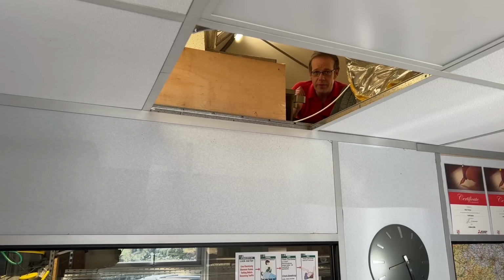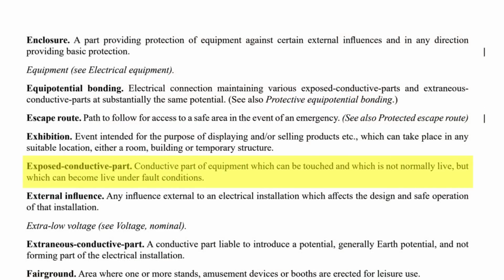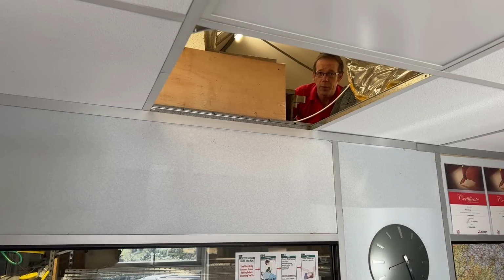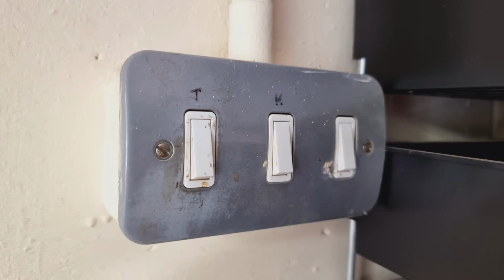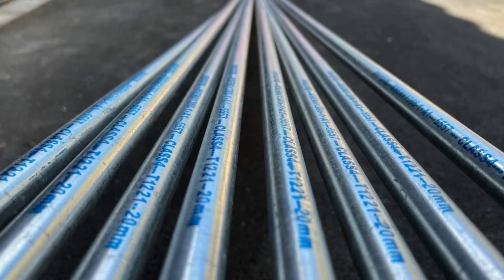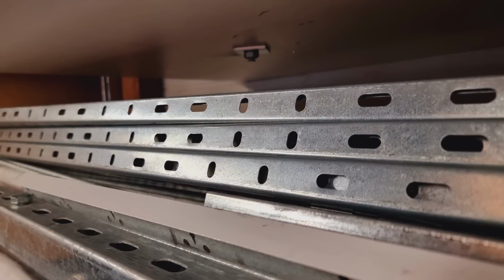Well, there's two types of conductive material in a building that may need connecting to the main earthing terminal of an installation, these being exposed and extraneous conductive parts, and BS 7671 defines them as follows. An exposed conductive part is a conductive part of equipment which can be touched and which is not normally live, but which can become live under fault conditions. The simple way to remember it is that this is a metal component which is actually part of the electrical installation and which can become live under fault conditions. So things like metal casings of single insulated equipment and containment like conduit or trunking, although not cable tray, as we've explained in another video.